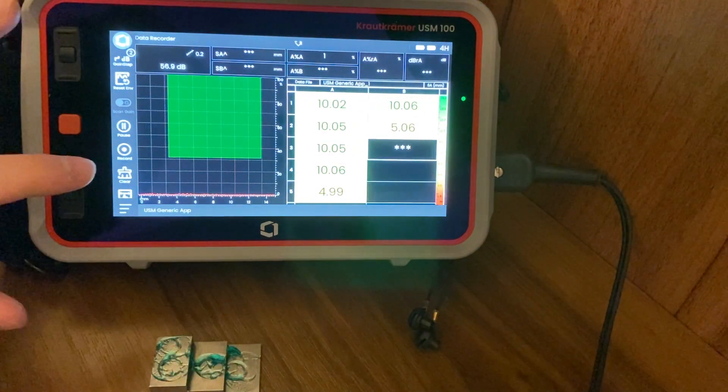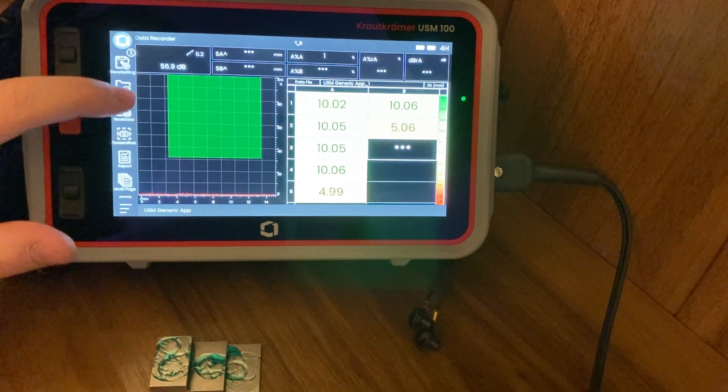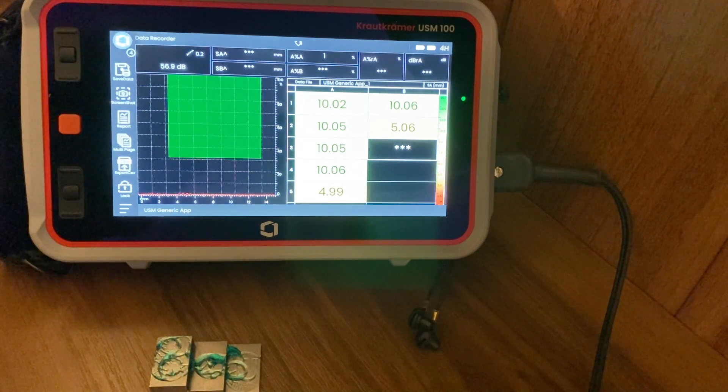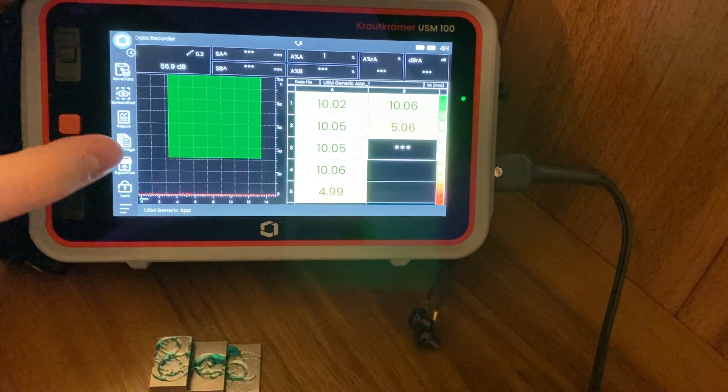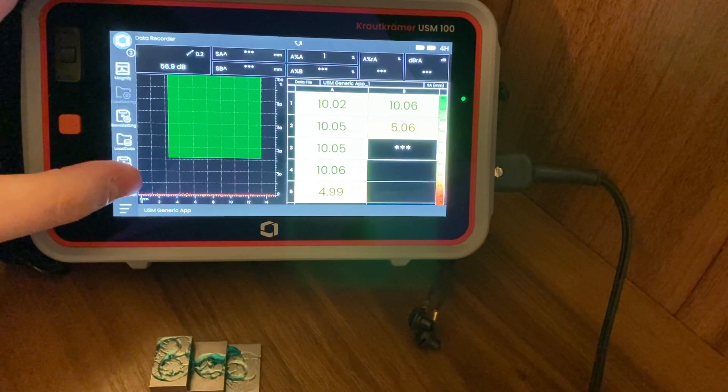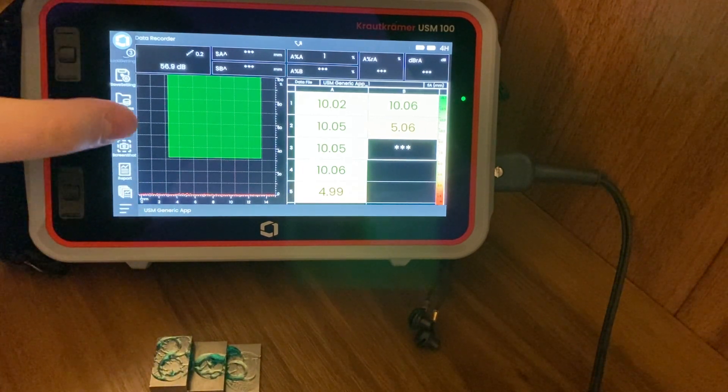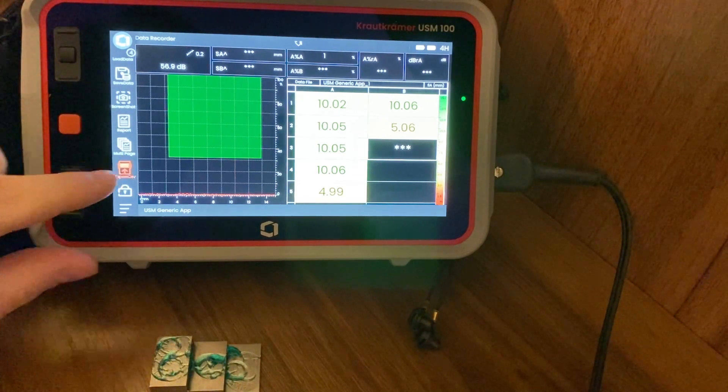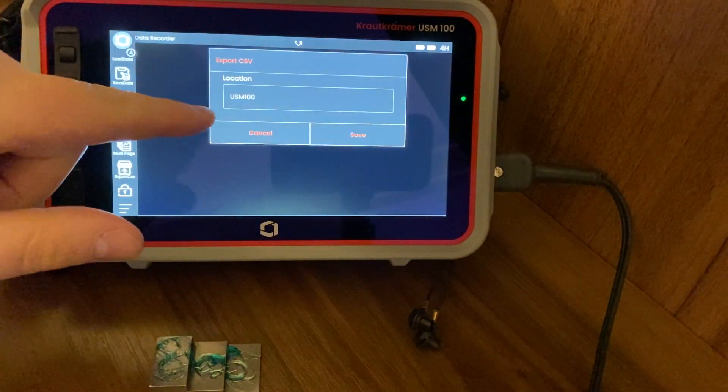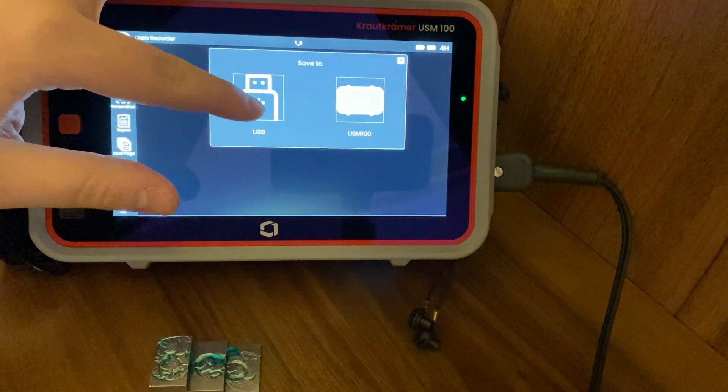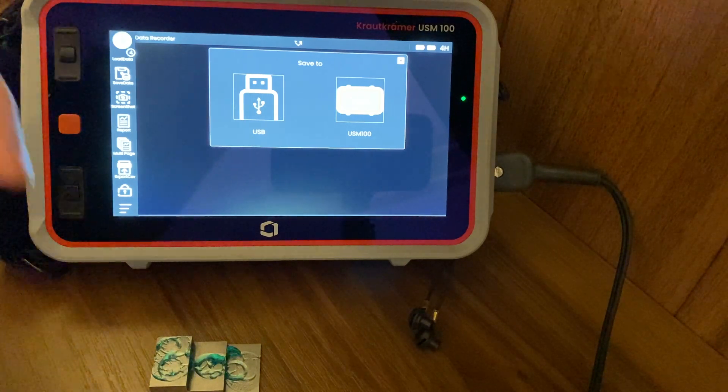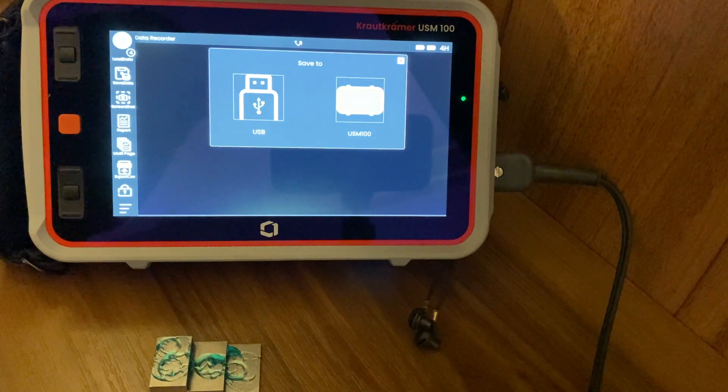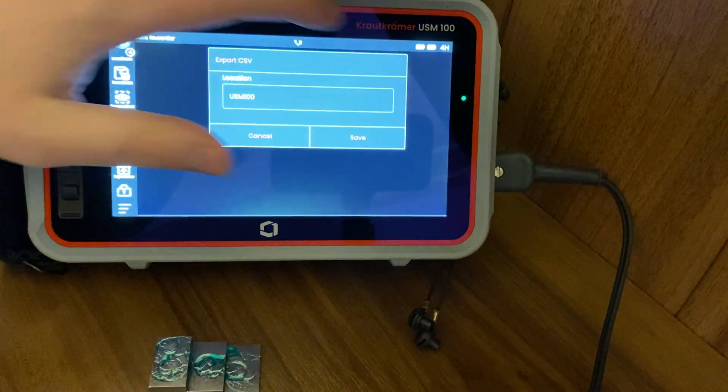Then you have the option - you can generate a report directly off the system, or if your customer requires you to use their template but you want to get the data out of it, what you simply do then is go to Export CSV. I simply tap on this button. It asks me to save it. If I had a USB in the system here, it would give me the option to USB by tapping here. I don't have a USB, so I can't save it onto it, but you save it onto USB, plug USB into your laptop, or you can use wireless transfer.